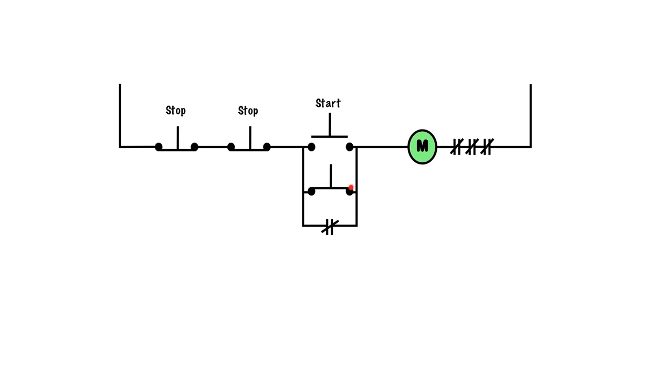Now let's press down on the second start pushbutton that's at a different station. When we press down on that, power can come through. It can't go across this start, but it can go down and go through this start, which will energize the coil, which will close these contacts and go through and go out the other side. When I let go and the normally open bounces back to its normally open position, these sets of contacts are closed, and therefore it holds it in, and M stays energized.